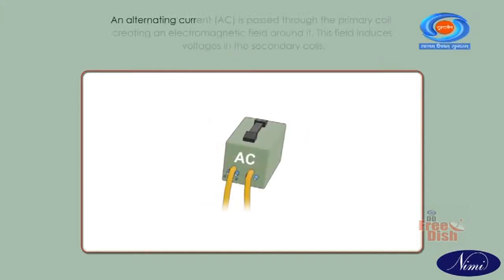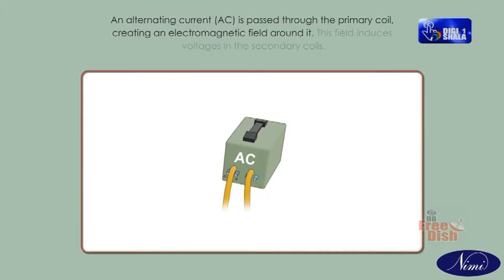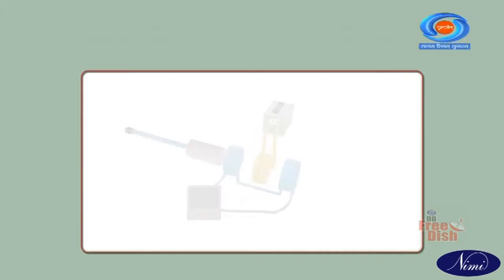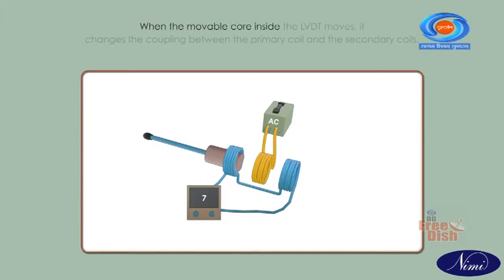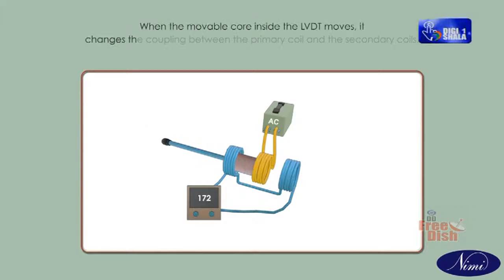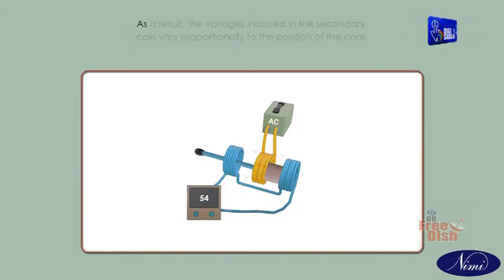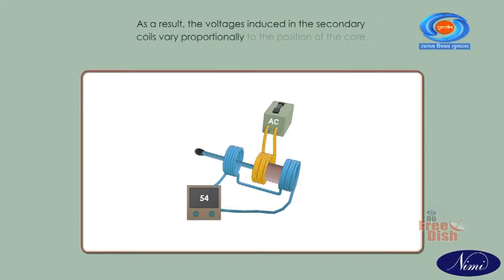An alternating current, AC, is passed through the primary coil, creating an electromagnetic field around it. This field induces voltages in the secondary coils. When the movable core inside the LVDT moves, it changes the coupling between the primary coil and the secondary coils. As a result, the voltages induced in the secondary coils vary proportionally to the position of the core.